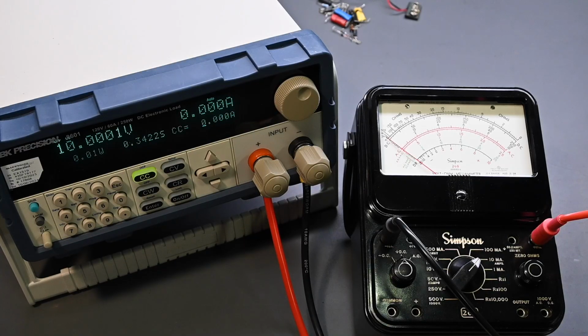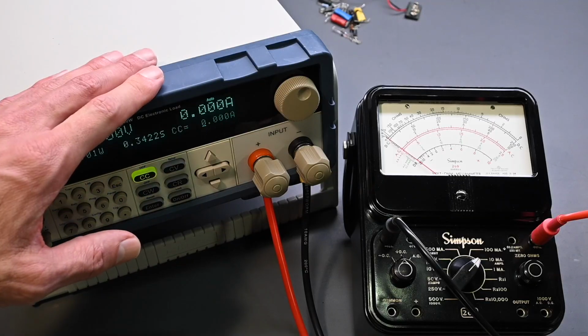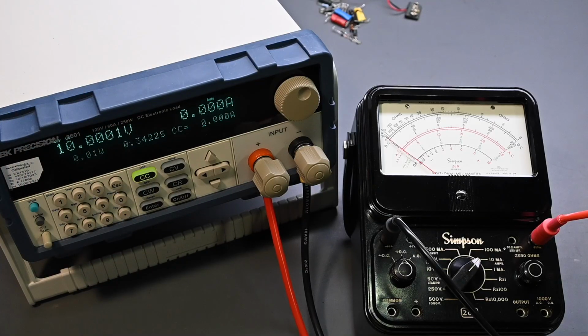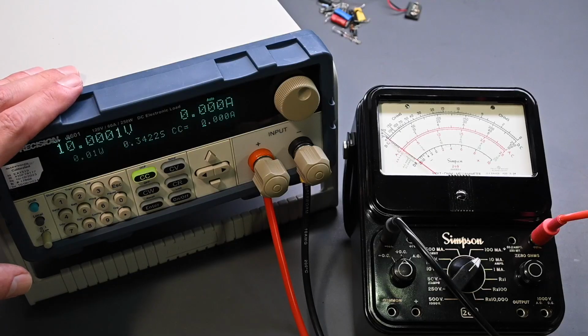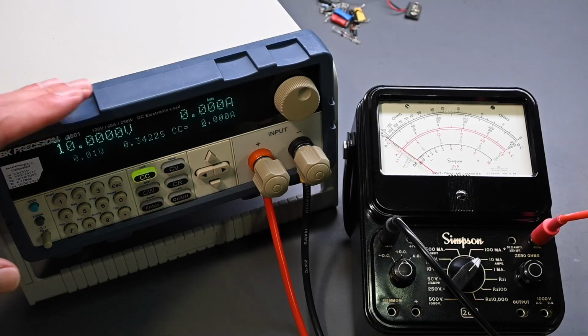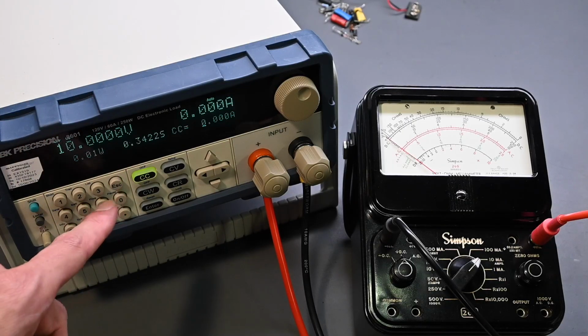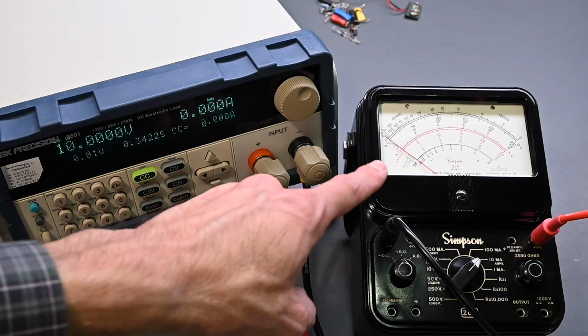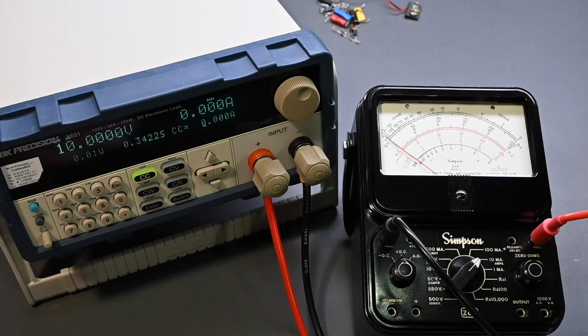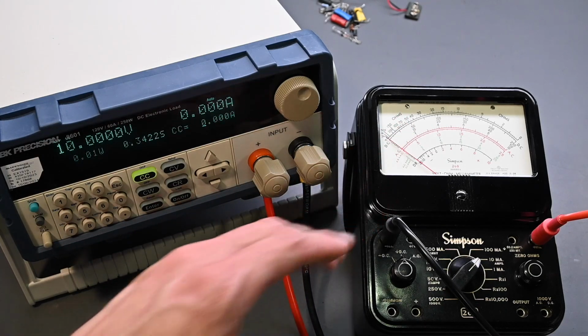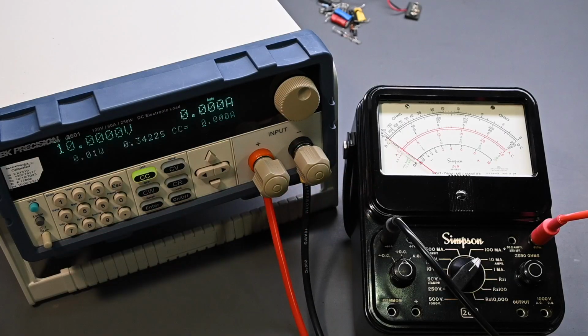So I have a large DC power supply connected to this electronic load. You can probably hear that fan running in the background. That's that big Sorensen SRL 40-25. So it's a 0 to 40 volt, up to 25 amp capability. I have it set to 10 volts, and you can see that's being displayed on the electronic load. I'll step the electronic load all the way up to 10 amps, and we'll watch for the indication on the Simpson 260. So the 260 is just connected in series between this electronic load and the power supply.